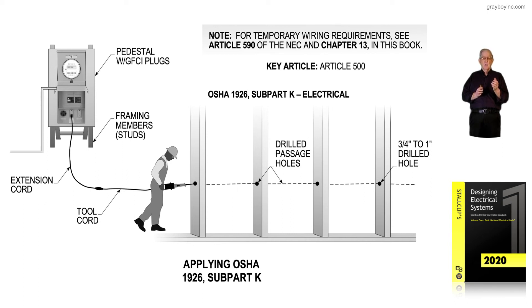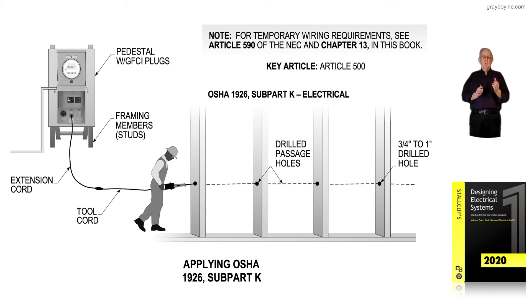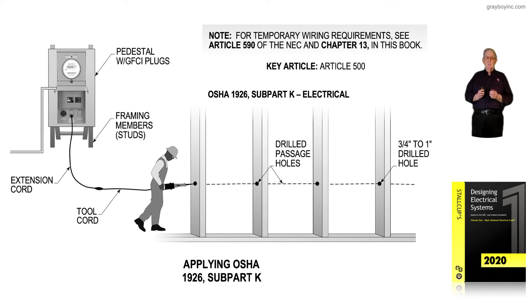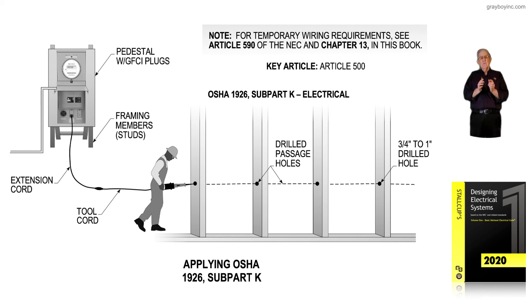What kind of switch is it? A single-pole switch? A three-way or four-way switch? If you were changing out a receptacle, then 70B naturally is going to recommend the use of Article 406. What kind of plug is it? Is it a GFCI plug? Is it an AFCI plug? Is it a regular plug? Is it a duplex? Is it a single? So we need to know the NEC well enough as a maintenance person to reference the section that deals with what we're trying to replace one-on-one under maintenance conditions.